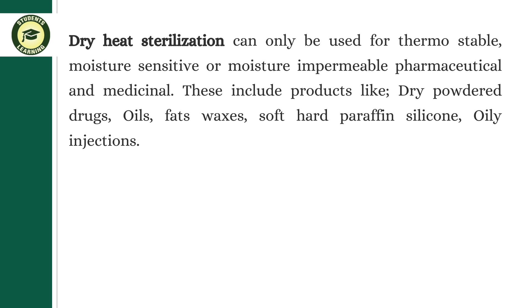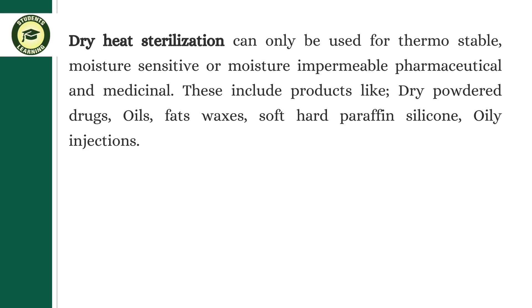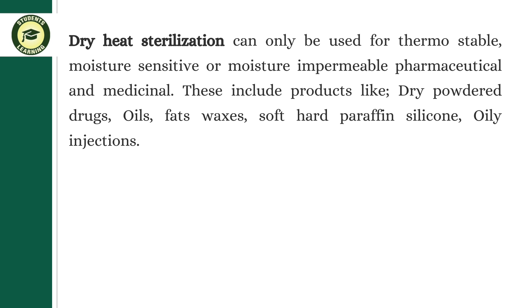Dry heat sterilization can only be used for thermostable, moisture-sensitive, or moisture-impermeable pharmaceutical and medicinal products. These include dry powder drugs, oils, fats, waxes, soft and hard paraffin, silicone, and oily injections. Due to its good penetrability and non-corrosive nature, it is one of the best techniques to sterilize metal surgical instruments and glasswares.